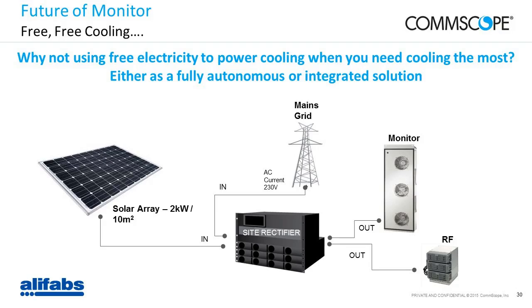The solar array delivers up to a couple of kilowatts, but it needs to be clean. It's very dirty DC power. It needs to be cleaned, and that can be done through different types of system, through modern rectifiers, as you know them, from different suppliers. So when you need cooling the most, in the middle of the summer, you can power your monitor free cooling system directly from a solar array. Meanwhile, if you don't need cooling that much, in the middle of the winter for example, and you barely need power for the cooling system, you can use it for the RF equipment, which is more of a priority.